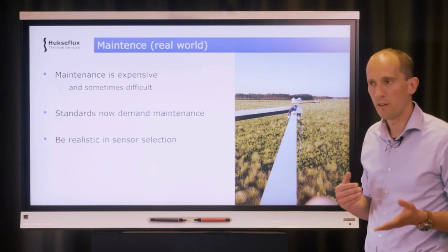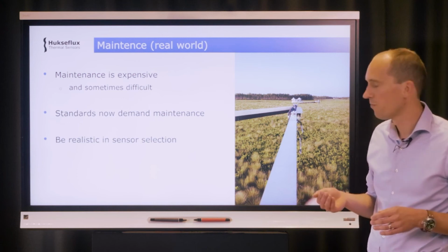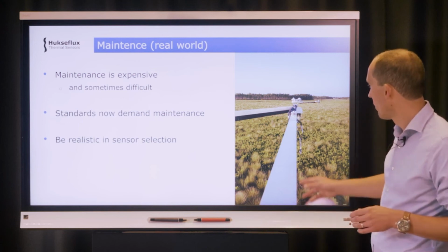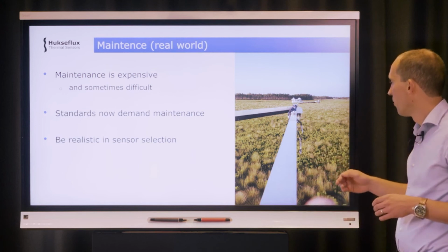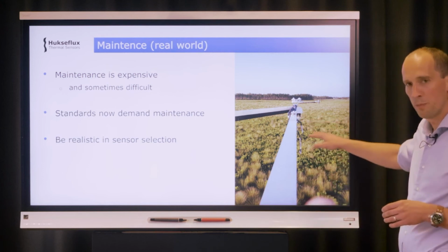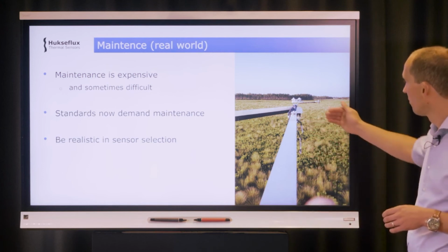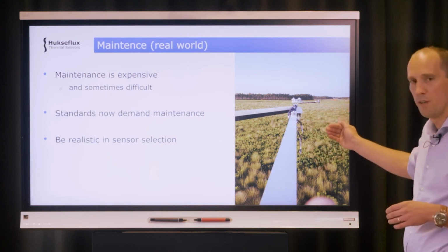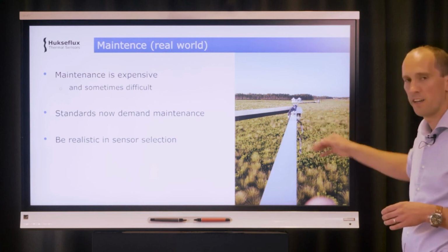Pyranometers are mounted in remote locations. This is a picture of a site in the US where they have a net radiometer installed on an arm, and after installation they see this arm, which is like 8 meters long, is actually, this instrument is slightly out of level.